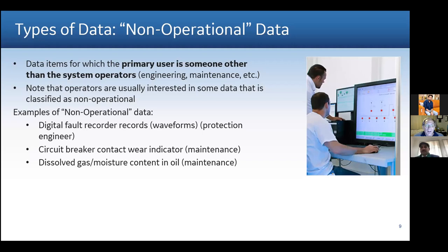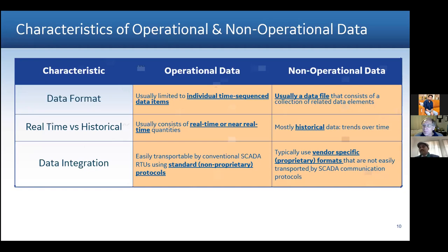So non-operational data is points or files, like a digitized waveform or a sequence of events report. This is information that the operators don't need in the control center, but there's 25 to 30 other groups in the customer organization that have a need for this data. These are the characteristics between operational and non-operational data. Non-operational is on demand, it's typically historical, and it's both points and data files. Operational data is what we're used to sending to the control center for many, many years.